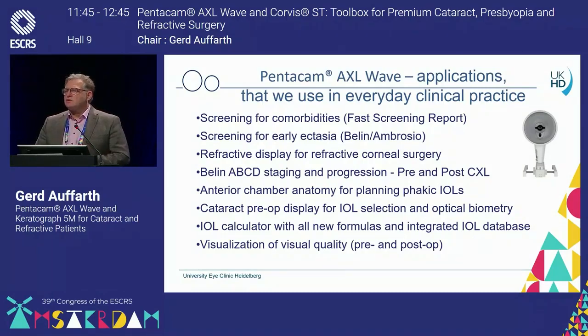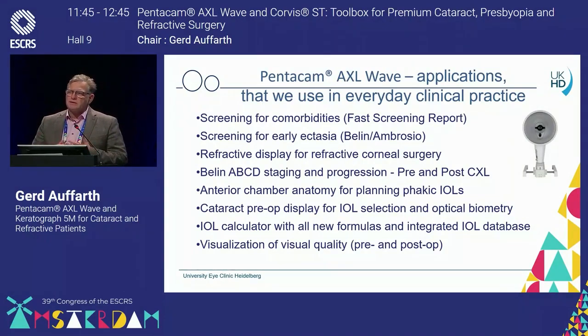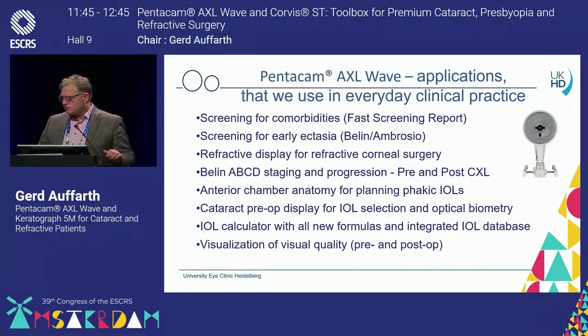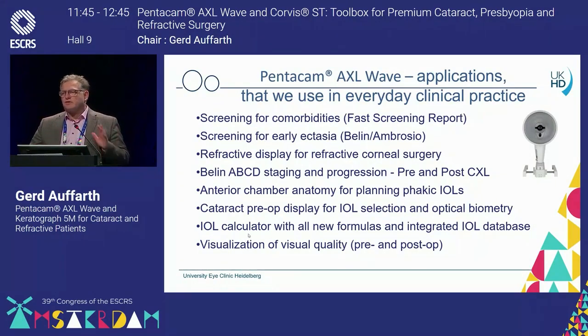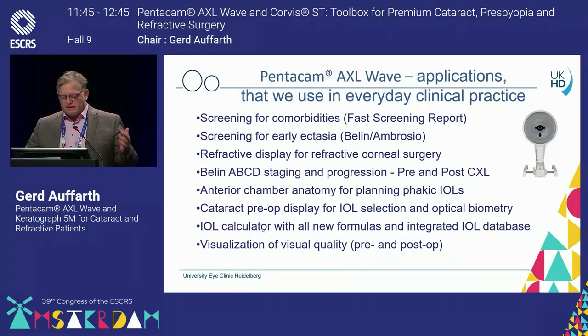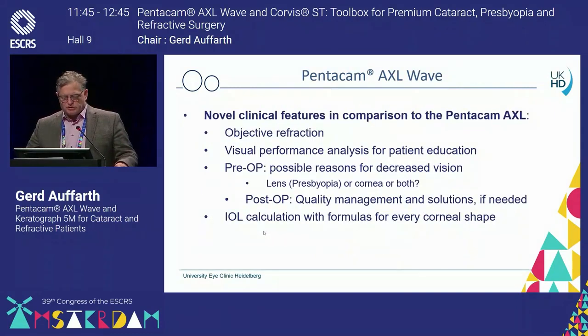And last but not least, especially now added with the wavefront measurement, you get a whole and total wavefront and you can separate between the corneal and the internal wavefront and the entire wavefront. You can also give the patient a display where you can show them what's wrong or what the problem is, so they better understand when you have to do some treatment pre or post-operatively.